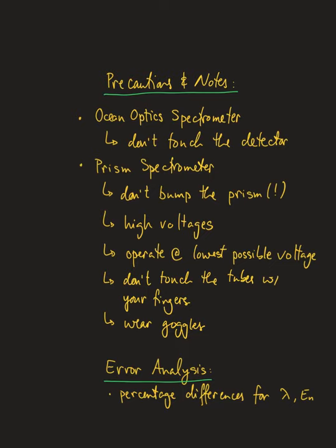As mentioned earlier, there's a high voltage across the spectrum tubes, and so don't put your fingers in there or something. Be very careful. When you're replacing the tubes, you should unplug the spectrometer power supply from the LabVolt one.